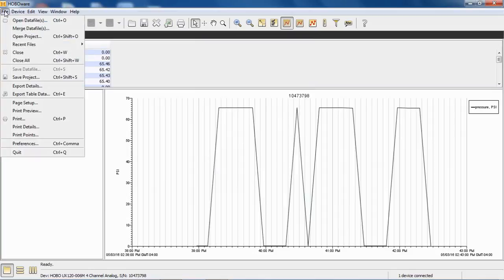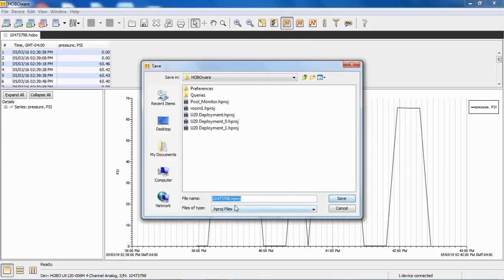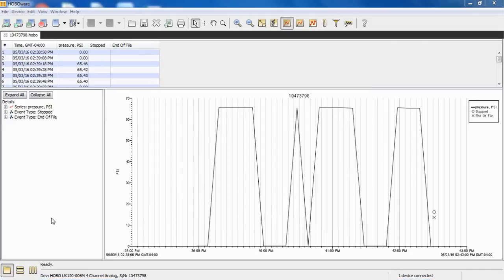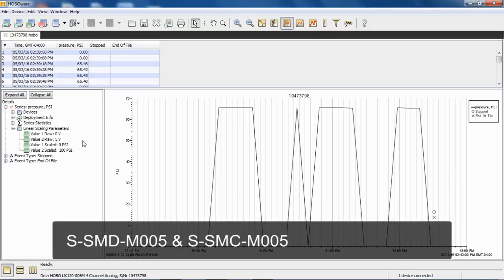If we want to save this, we would go to File, Save Project, and then give it a name, and it will retain this scaling. Otherwise, the next time we open it, it will be in voltage also. And if you wanted to confirm what scaling parameters were used when the logger was launched, or what was used for the post-processing parameters, you go over here into the details pane on the left, click on the little plus sign in front of series pressure PSI, and then scroll down through this list: devices, deployment info, series statistics, and here we have linear scaling parameters. If we click on the little plus sign, it'll tell us what was used to scale that analog input.